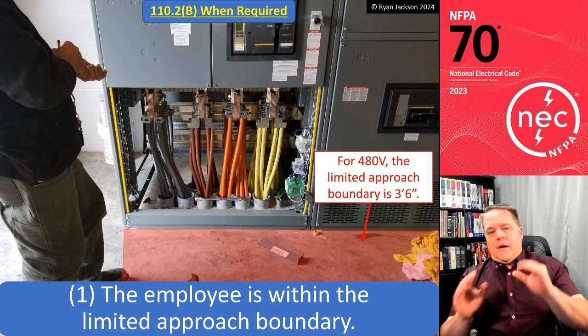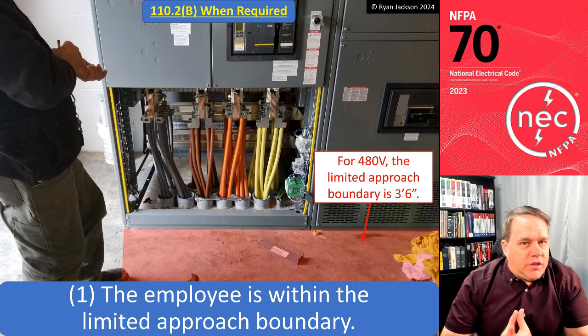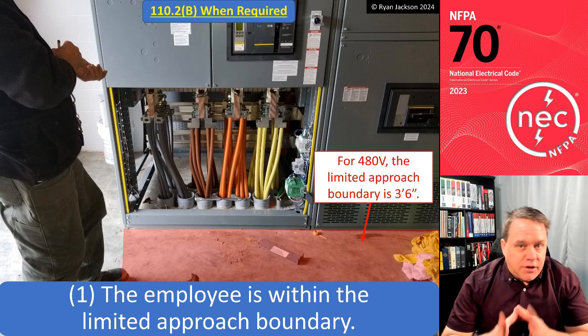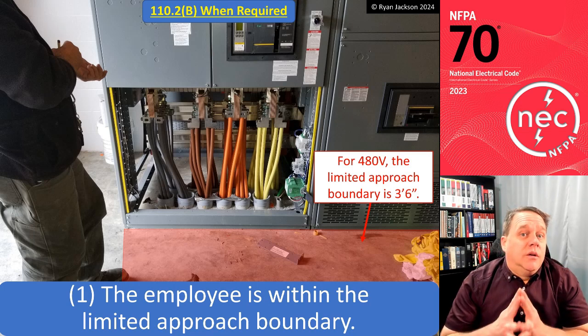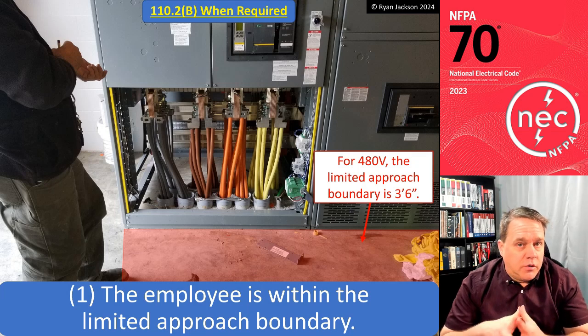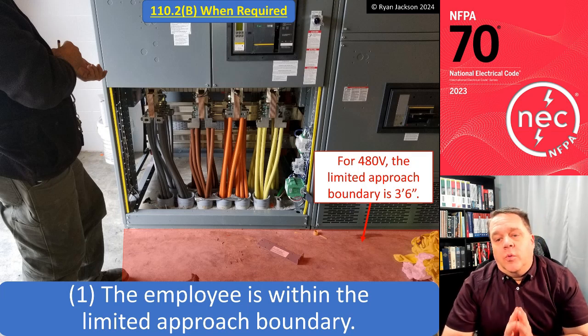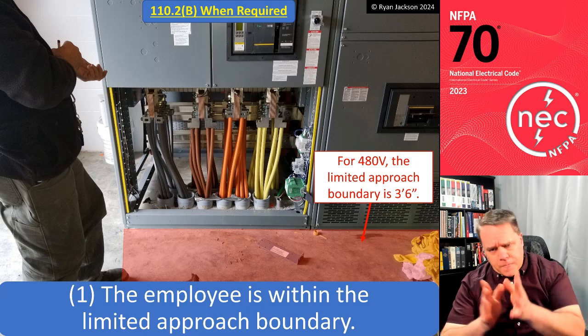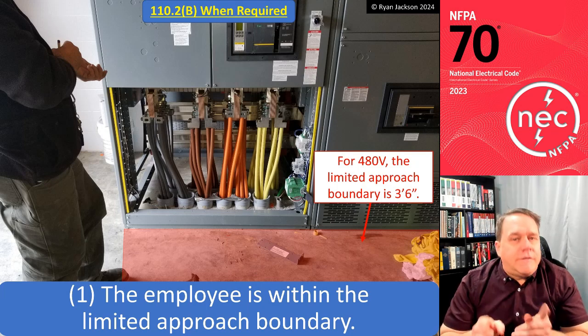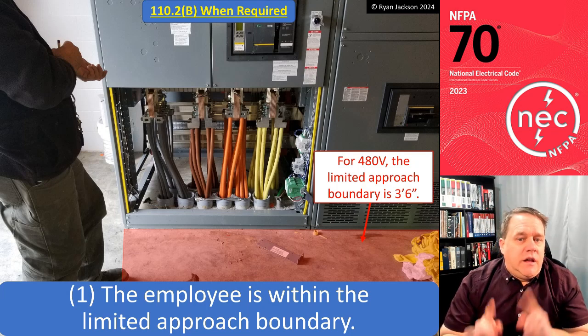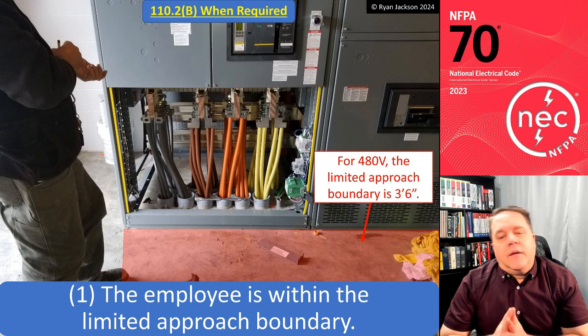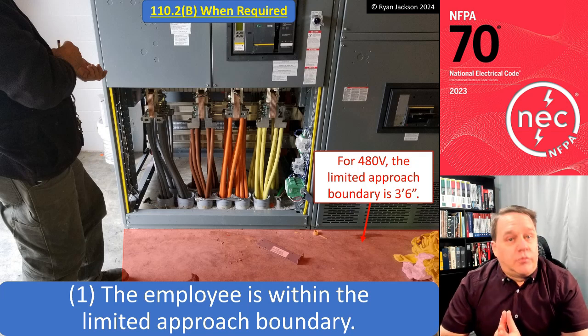All right. So we haven't talked about what the limited approach boundary is yet, but the limited approach boundary is a shock protection boundary. It has nothing to do with arc flash, has everything to do with electric shock. So here in the photograph, if this is energized and if this is 480 volts, the limited approach boundary is 3'6".